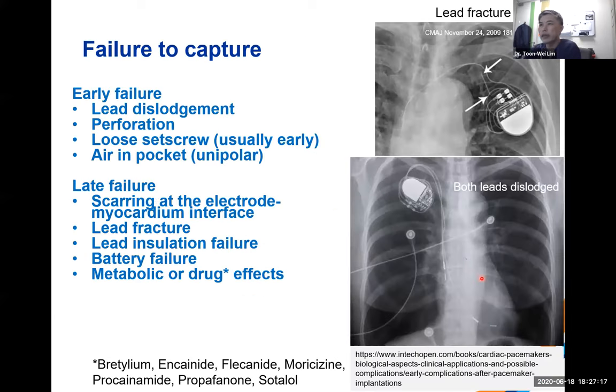In terms of early failures, there will be things like lead dislodgement. As you can see in this X-ray down here, clearly the atrial lead has really retracted and is no longer in its implanted position. The ventricular lead probably is still in position, but that probably needs to be checked as well. And then the other things are when the pacemaker lead has perforated the ventricle, or whether there's a loose set screw because the screw wasn't screwed in properly. And rarely also things like where there's too much air in the pocket, especially if it's a unipolar pacing system.